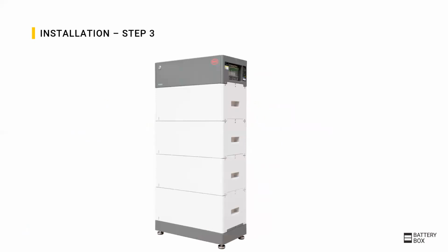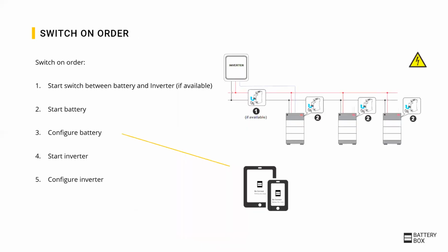After the cabling is complete, the next step is commissioning. For this, the battery needs to be activated by the system switch on the right side of the BCU. Here, the correct switch on order is important. If there is a switch between the inverter and the battery, that needs to be turned on first. After this, the battery needs to be started and configured.